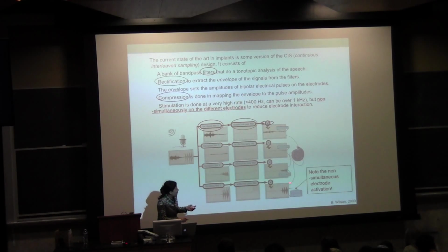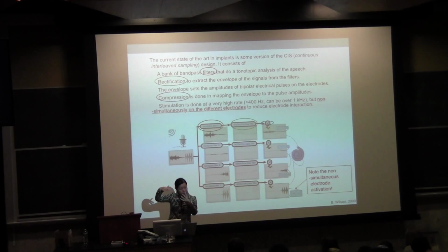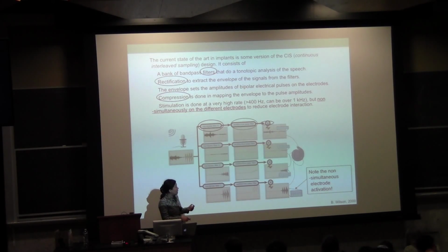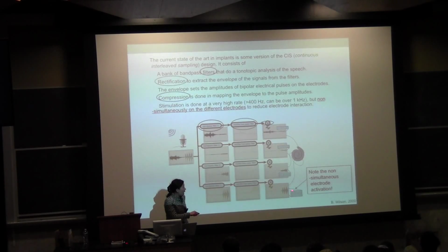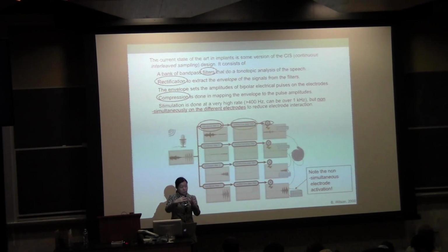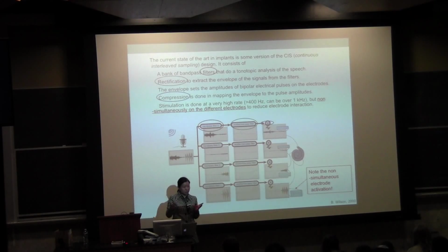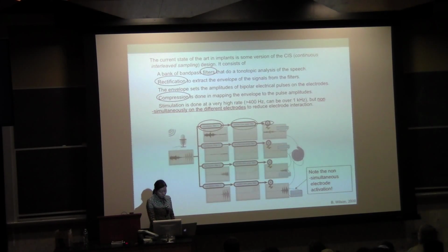What is interleaved? Interleaved here means, for the electrical pulses, to avoid the overlap of the excitation pattern along the electrode array. So there are no simultaneous electrical pulses across all the 22 electrodes. The first pulse of channel 2, channel 3, channel 4 would be offset from each other, so that at one time there are no two pulses being sent to the electrodes. That avoids the interaction across all the electrodes. That's a very successful strategy.